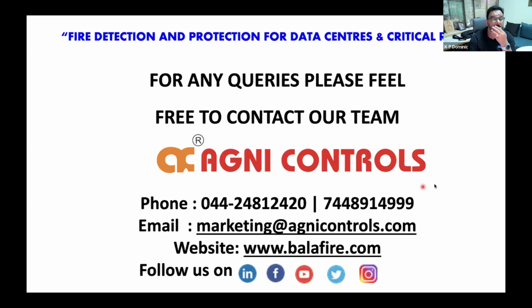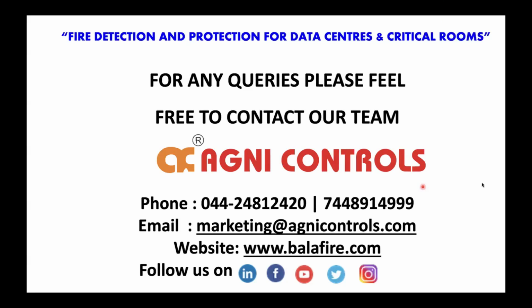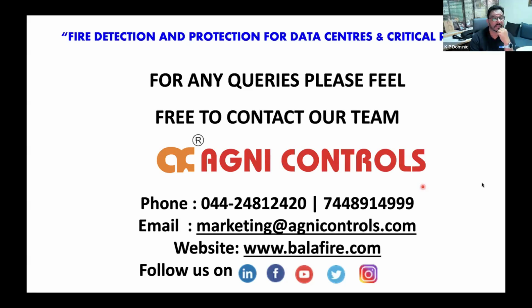So that I'll skip. What type of extinguisher can we use for finished goods edible oil in an ASRS storage system? Oil, edible oil boxes in an ASRS storage system. For oils, dry chemical and foam. For oils there are also class K type extinguishers available for oil fires, so that can also be used. Again, Pandiraj is asking, what kind of detector can be used for the ASRS storage system?